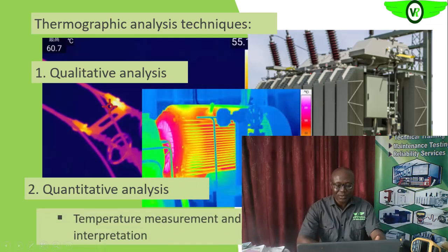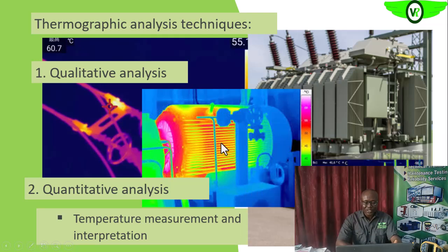So this is what I was saying. You take the spot temperature by moving your pointer in your thermogram to the spot, and then you take the ambient. This could give you the ambient because this is a frame that is not connected to the electric motor, so it has direct connection with the ambient.